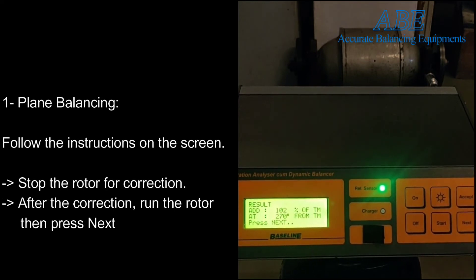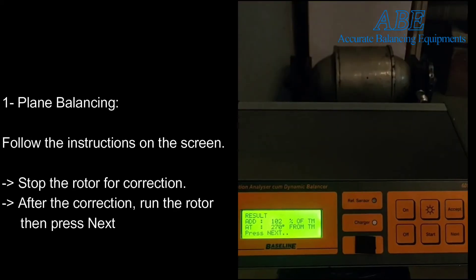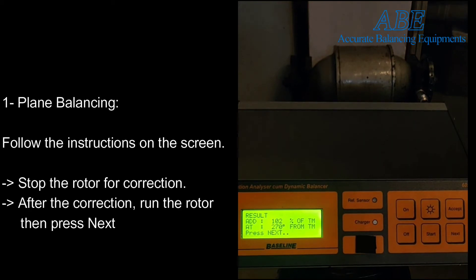Once the result comes, stop the rotor for the correction. The instrument is indicating that you need to add a weight that is 102 percent of the trial mass, and it is to be added at a position in the increasing direction, 270 degrees from the trial mass. After performing the correction, the unit will give you the option to save the constants, and then you can take a verification run to see the final vector.